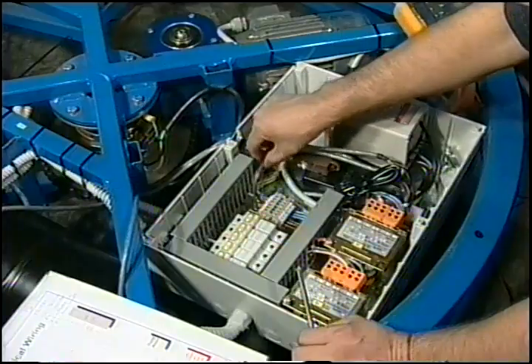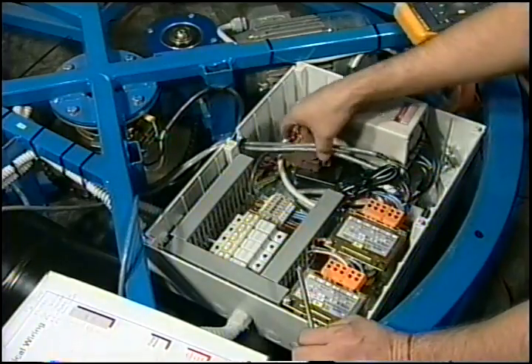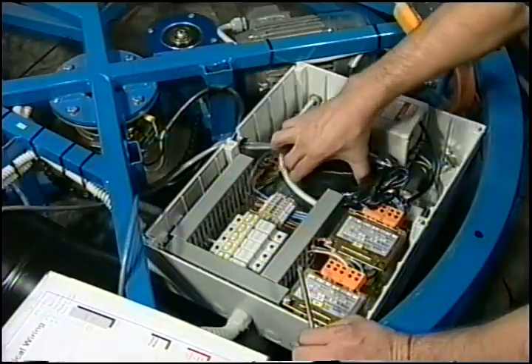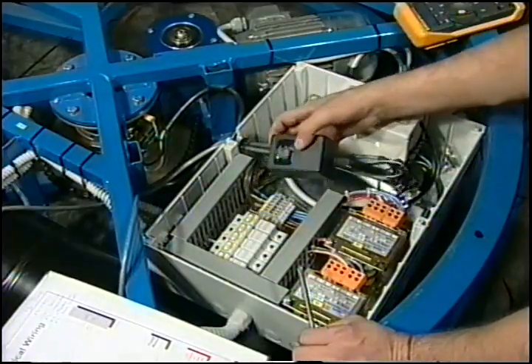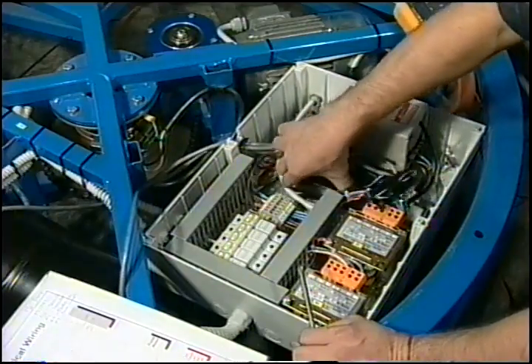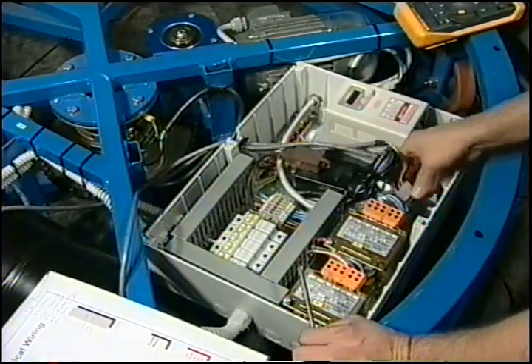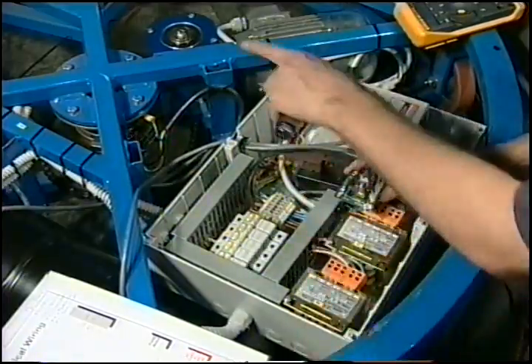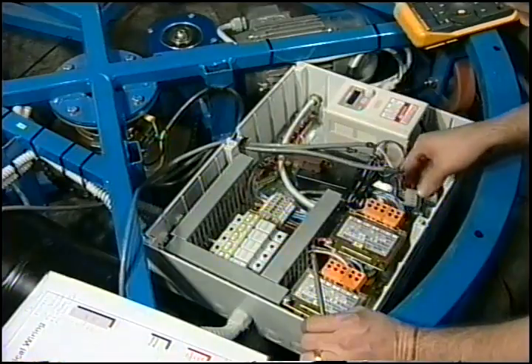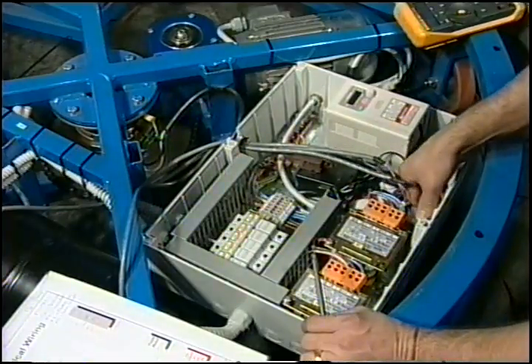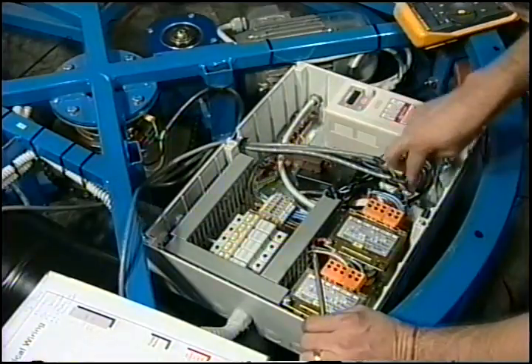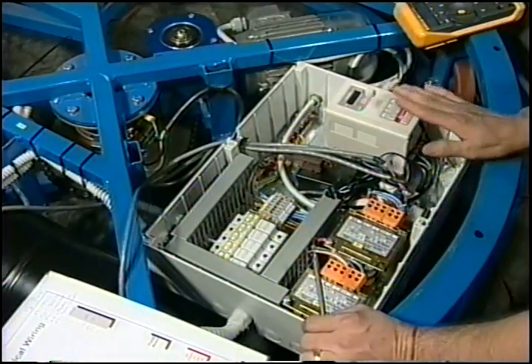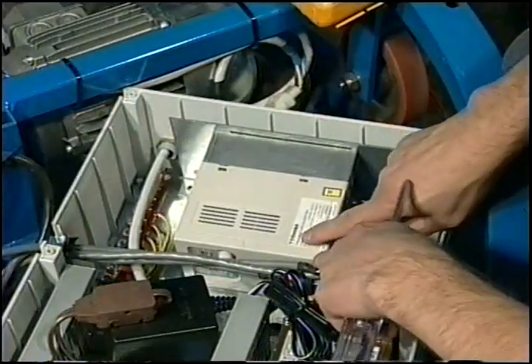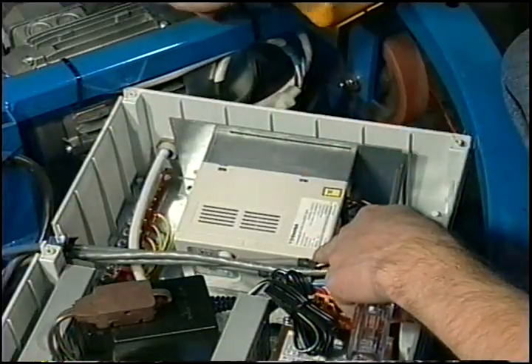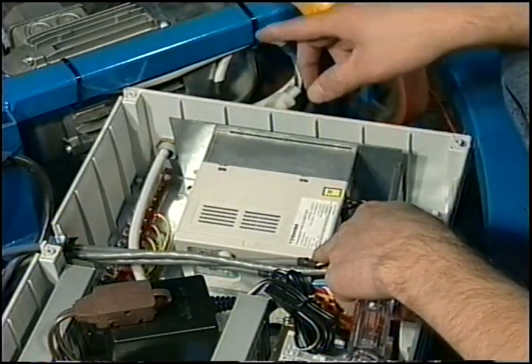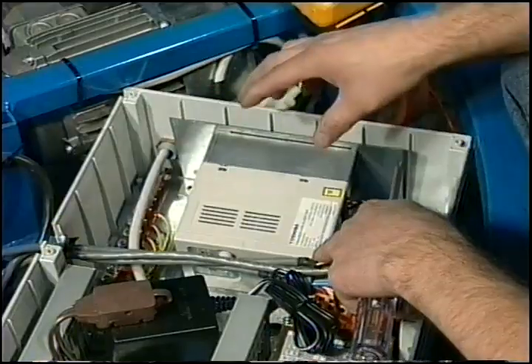Then your 120 also routes off of your main input here to a 12 volt AC adapter that's rated at 1000 milliamps. And the only use for this transformer is to supply 12 volts to your relay circuit that's for your base sensors. And we'll go into that a little further later on. The only other thing that your 120 supplies power to is your Toshiba inverter. Now you have your Toshiba transistor inverter. It's what controls your rotation motor, and we're able to set the frequencies and adjust how fast the base rotates.